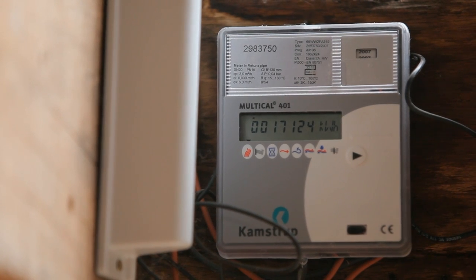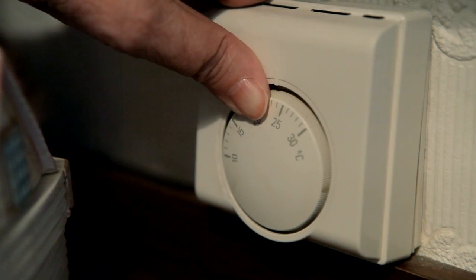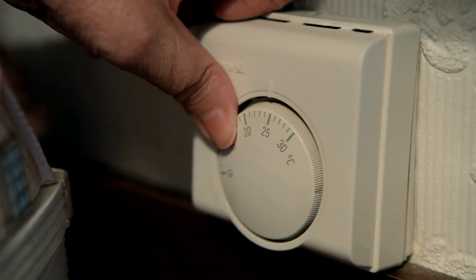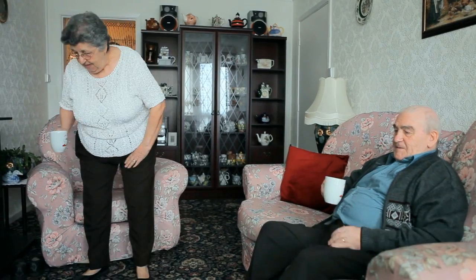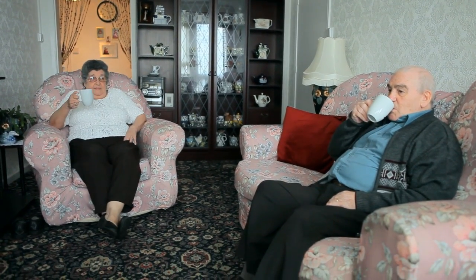Temperature measurement of the flow and return lines plus a flow meter together form a heat meter. This allows the actual heat usage within each building or even apartment to be separately measured. More modern systems, including biomass district heating systems, tend to use such a heat metering system, as it means that each building or home can be accurately billed for the kilowatt hours of heat they've used.